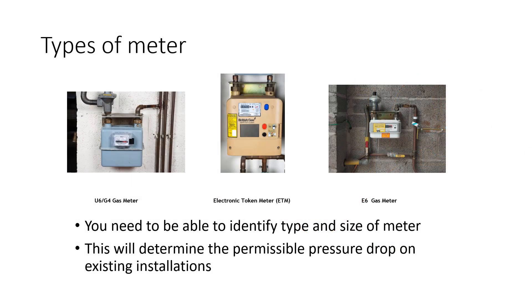When working on a system connected to the gas pipework that has a meter fitted, the first thing you need to know is what type of meter it is. Depending on what type of meter you've got, that determines the amount of drop in pressure you're allowed during your two-minute tightness test. Different meters allow different drops — this is called the permissible pressure drop — and it tells you how much pressure your system is allowed to lose within the two-minute test before it fails.